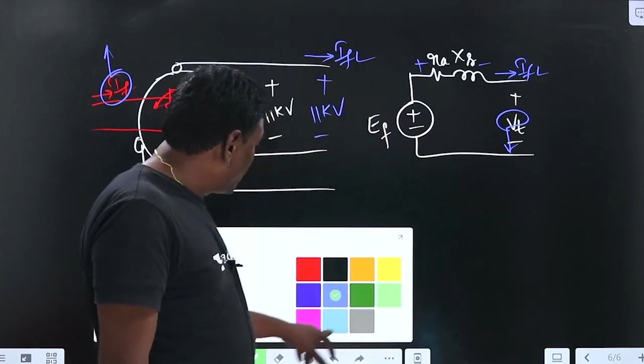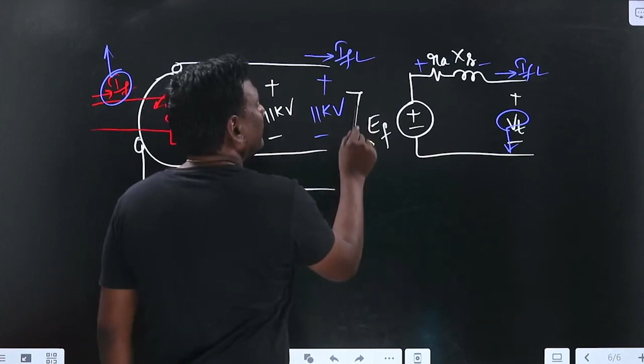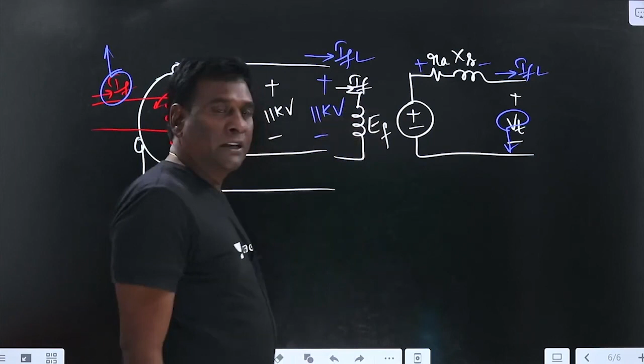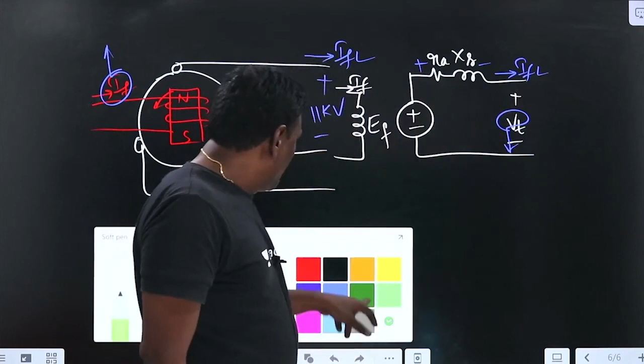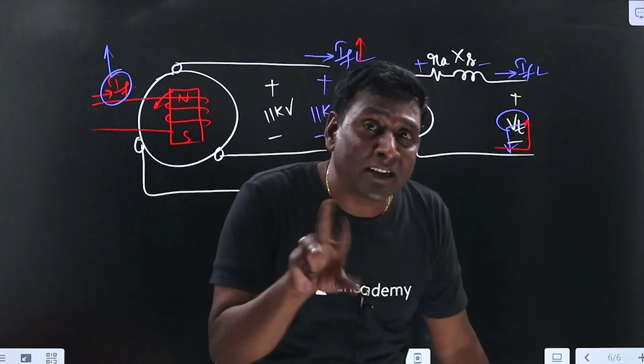Then what are you going to do? For this, the field is there, no? So this is going to be the field current at starting. Now the moment terminal voltage is reduced, in order to maintain terminal voltage constant, we are going to increase the field current. The moment you increase field current, automatically EF will be increased, or automatically terminal voltage will be increased, such that at no load, if it is 11 kV, at full load also it is going to be 11 kV only. Now my terminal voltage variations are not going to happen for the alternator.